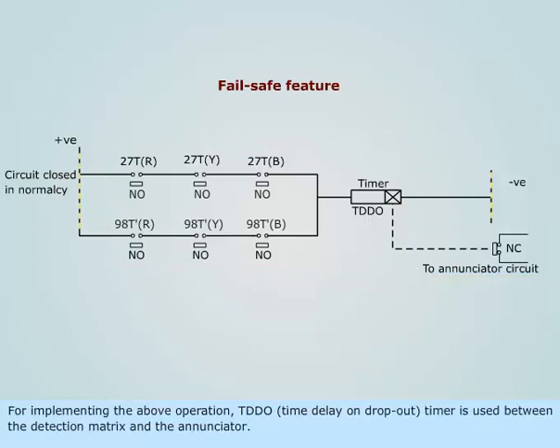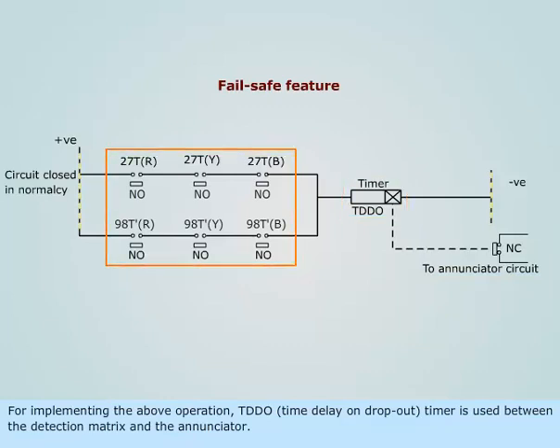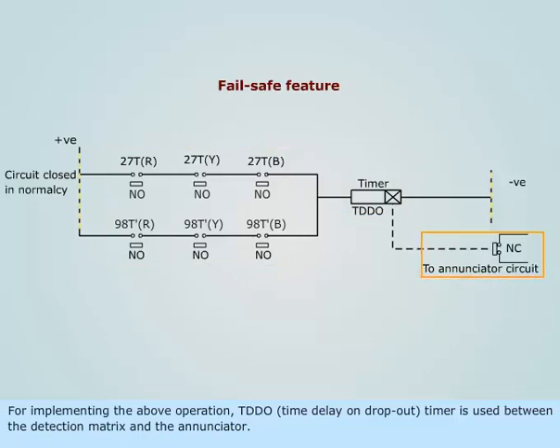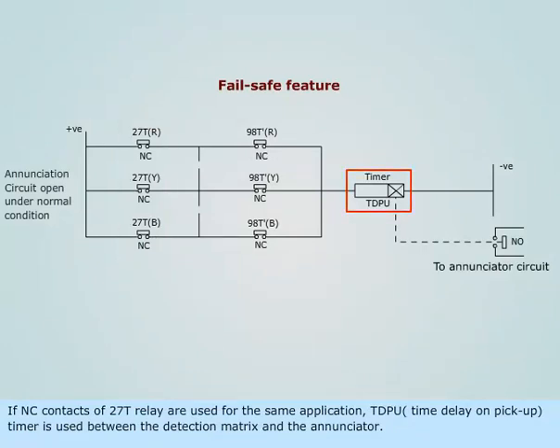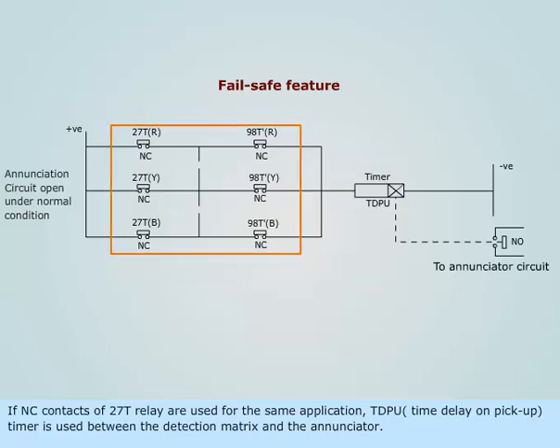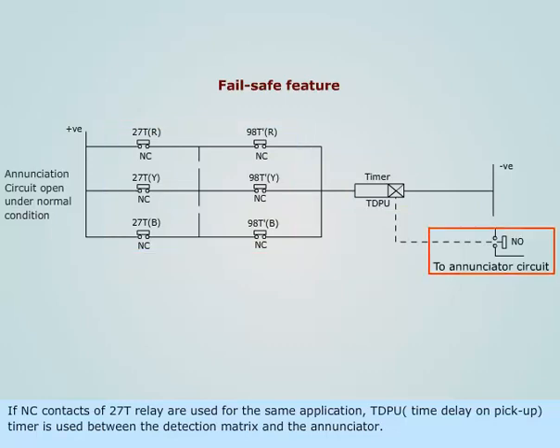For implementing the above operation, a TDDO (time delay on dropout) timer is used between the detection matrix and the annunciator. If NC contacts of 27T relay are used for the same application, a TDPU (time delay on pickup) timer is used between the detection matrix and the annunciator.